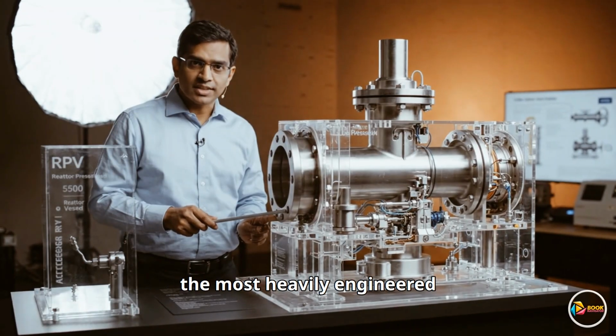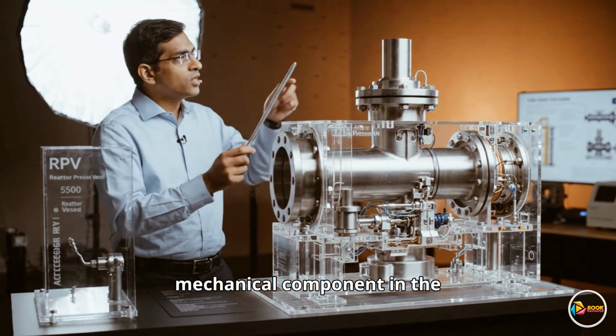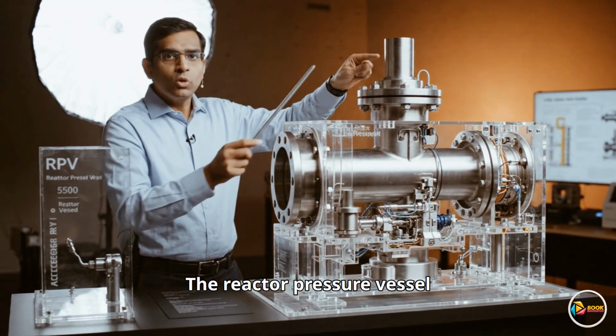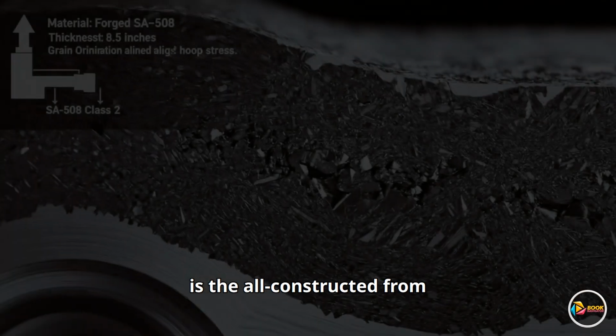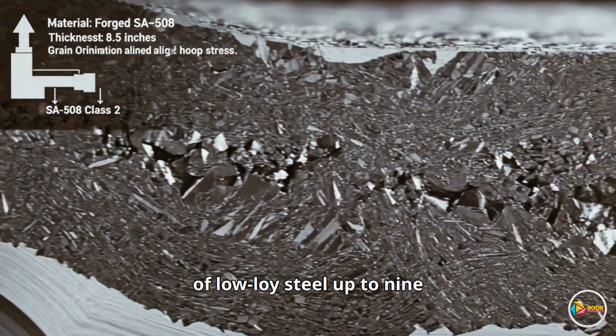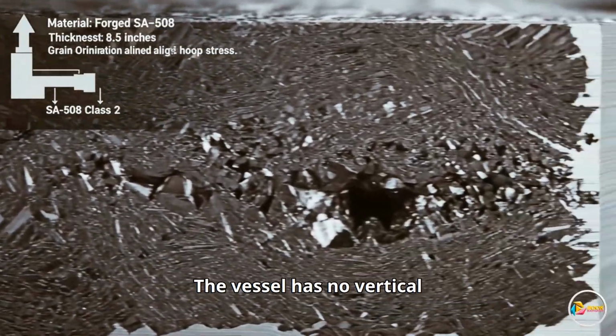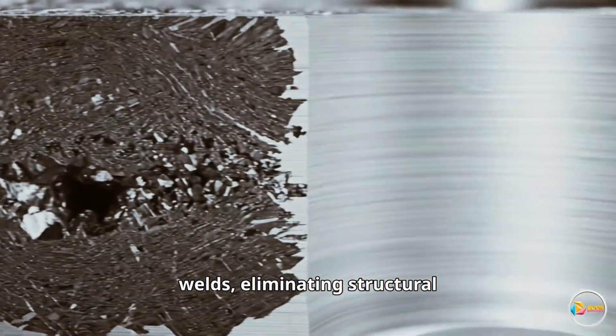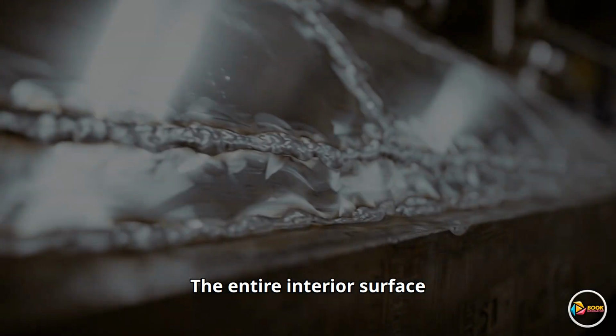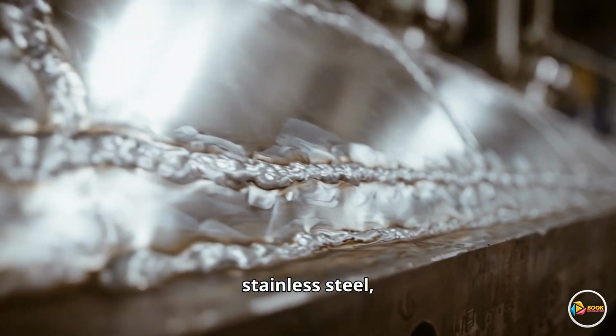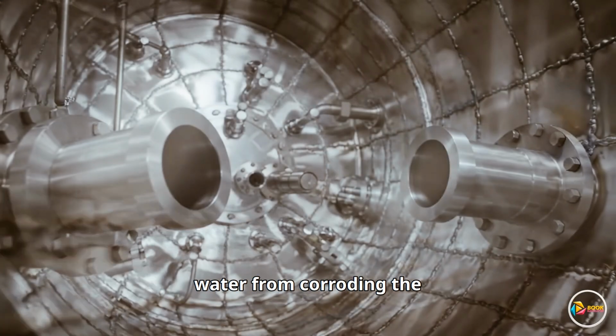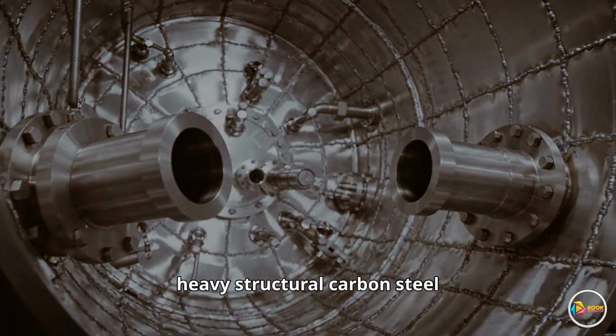This is the central pressure vessel, the most heavily engineered mechanical component in the entire facility. The reactor pressure vessel is constructed from massive seamless forgings of low-alloy steel up to 9 inches thick, and the vessel has no vertical welds, eliminating structural weak points. The entire interior surface is clad in high-grade stainless steel, preventing the borated coolant water from corroding the heavy structural carbon steel underneath.